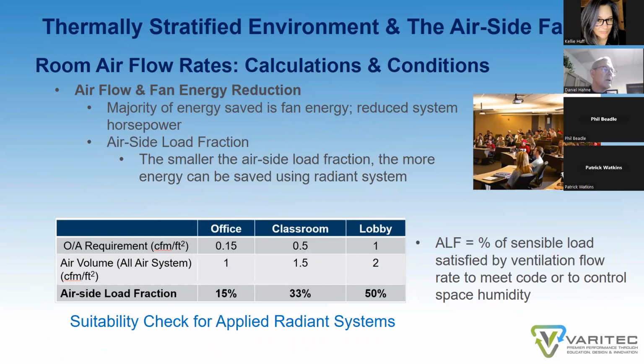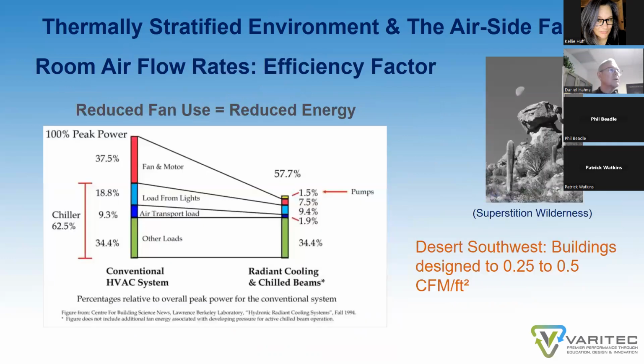From experience and because of the actual ventilation rate requirements for offices, classrooms, and lobbies, if you look at the airside load fraction rate for an office, it's at 15%. Offices, therefore, make all the sense in the world for applying passive radiant technologies. Classrooms, 33%. Lobbies even at 50%. So with this calculation, you can begin to assess whether or not passive radiant systems make sense for a design, make sense for the various zones within a building, and maybe a zone that would not make sense to apply it for by calculating what that airside load fraction value is.